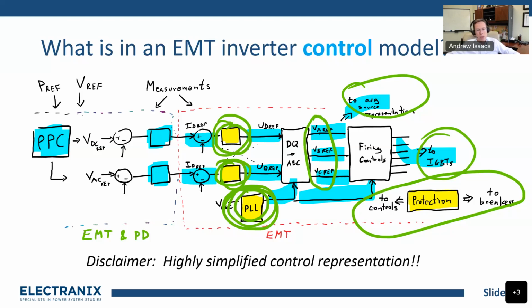Most of the time, to get a model that can properly represent those harmonic interactions impacted by the firing controls, you'll also need a lot more detail in your plant model and maybe your system model. By adding this switching noise into the system, you might get an artificial feeling that you can now see harmonic stuff, but it's not even really true. It runs a lot faster with average source representation, and you don't give up much by leaving out IGBT switching. So it's generally okay to use average source representation for most dynamic performance studies we do.